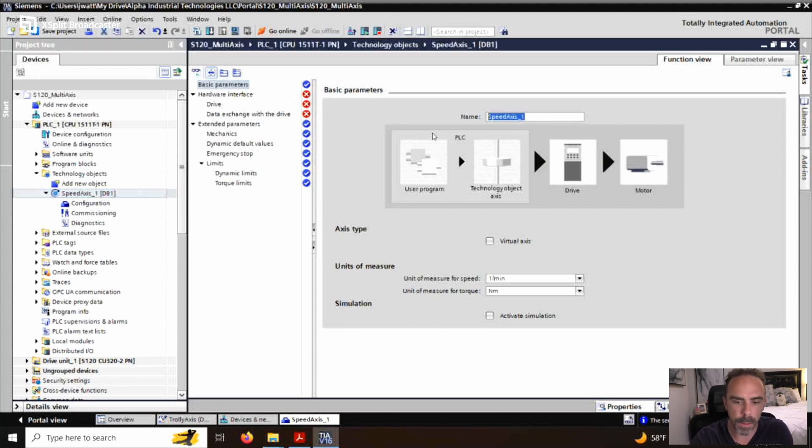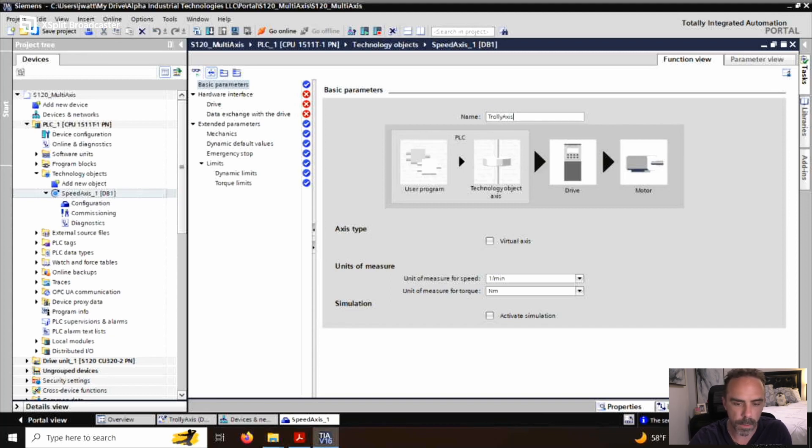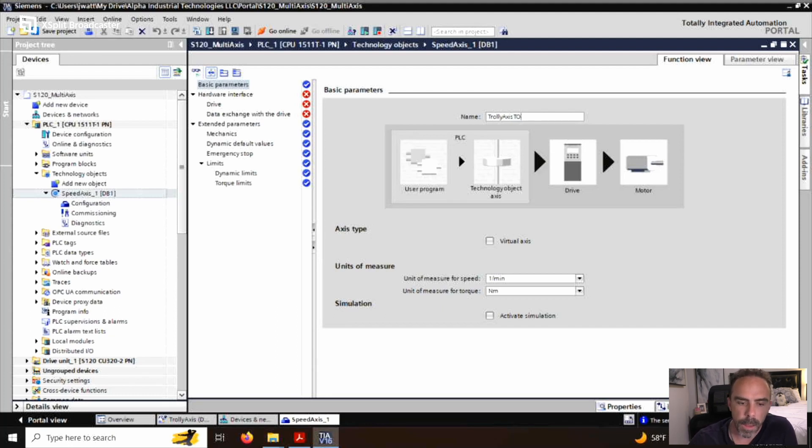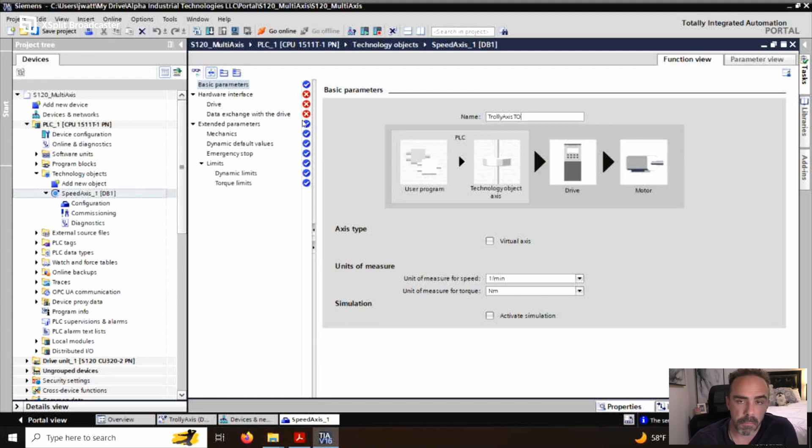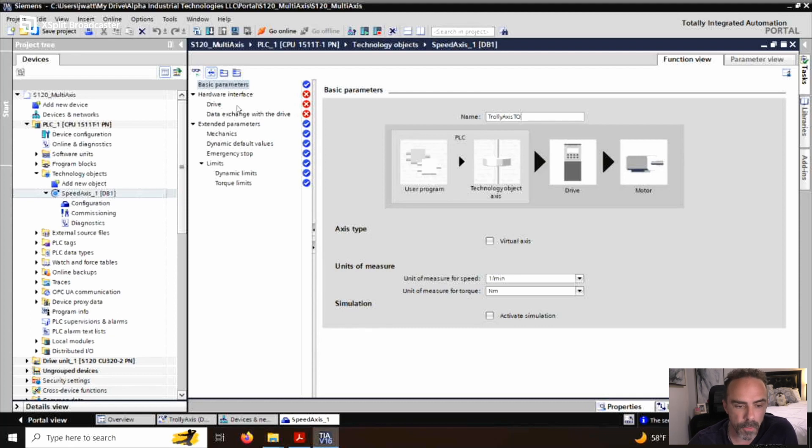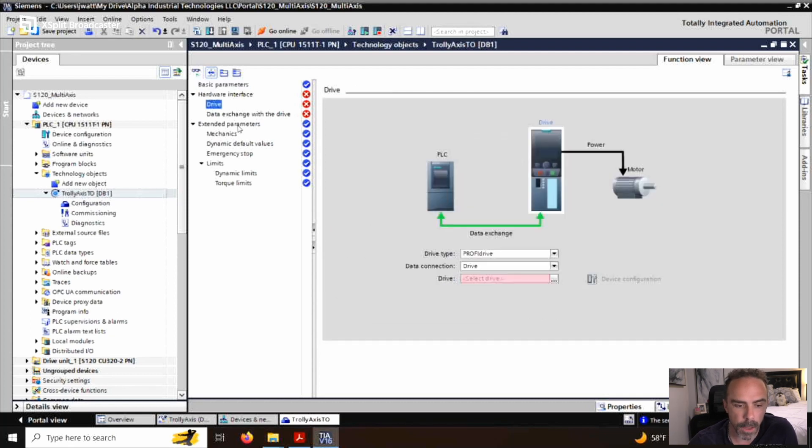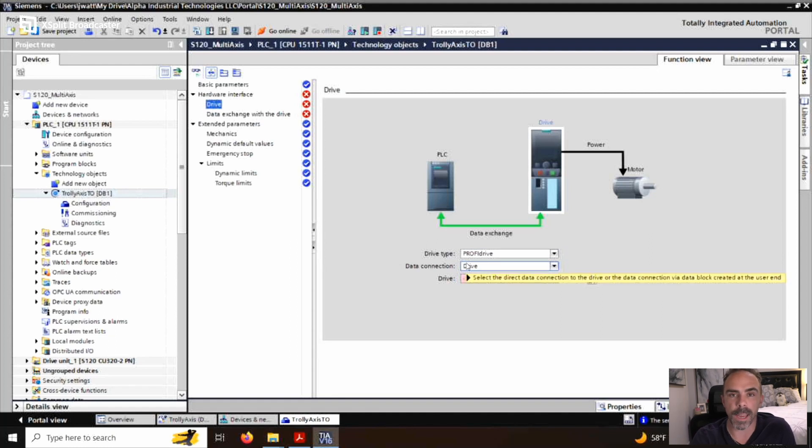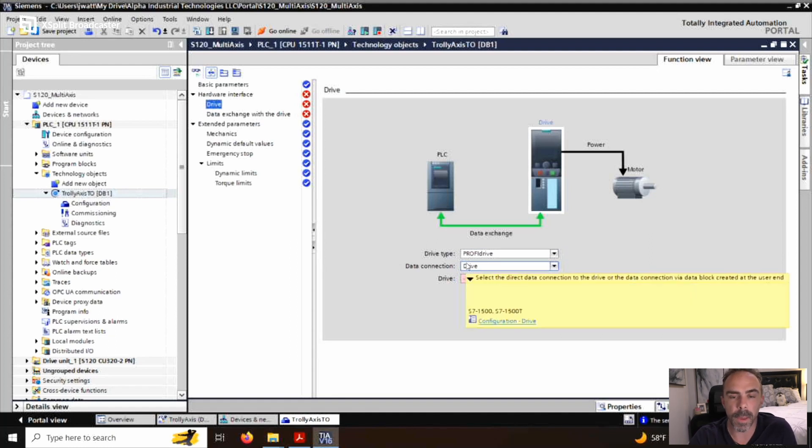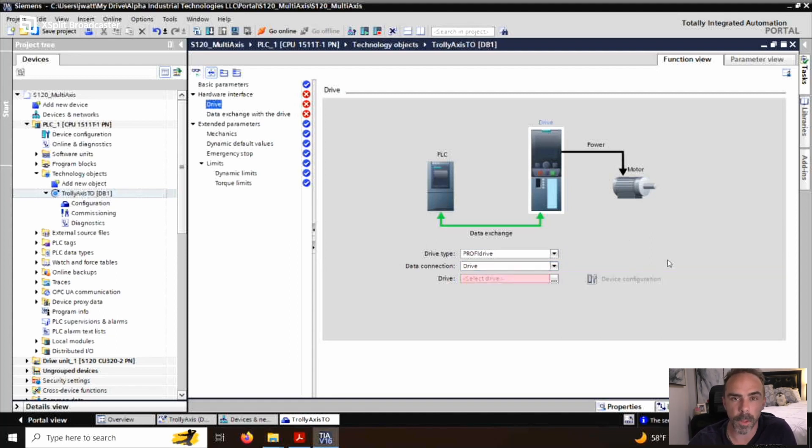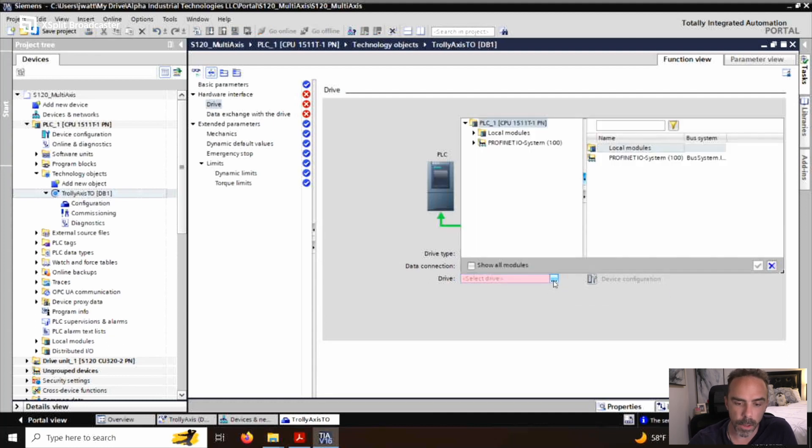I want to name this as a trolley axis TO. And that's what we're going to call it. Now, if you notice over here, there's a bunch of red, nasty looking red Xs. That means those parameters have not been set up yet. The first one I'm going to go to is set up a drive. All of my drives are communicating via Profinet to the PLC. I'm going to click on the dots. I'm going to click on Profinet IO system drop down.